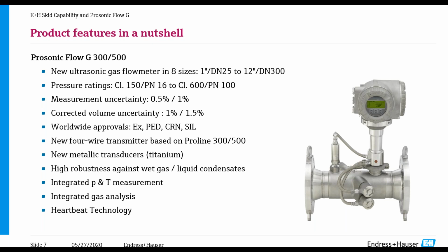And we specifically designed this meter for difficult applications, where you have wet gas or liquid carryover. A lot of times other flow meters fail in those types of applications because the condensate creates too much noise in the system. And we have some special features in here to combat that problem. We also have integrated pressure and temperature. If you're looking at the picture on the left, the piece sticking out on the left side is our pressure, and our temperature is located directly underneath the transmitter. So we have both pressure and temperature as an option.